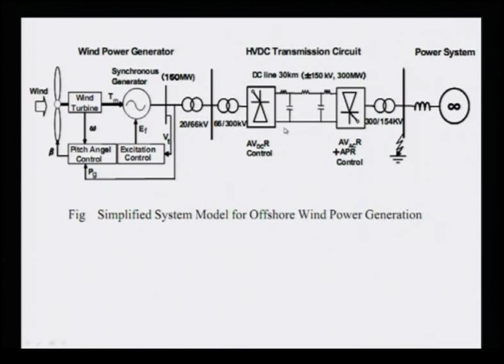But if you are using the VSC HVDC here, since there is no concern of commutation failure, we can recover the DC voltage rapidly. At the same time, with constant AC voltage control in the inverter, it can produce reactive power and help the recovery of the AC voltage as well. Thereby we can very quickly restore the voltage on this side, and the power system dynamics and whole AC/DC system operation using voltage source converter based HVDC improve much better than with the conventional HVDC system.